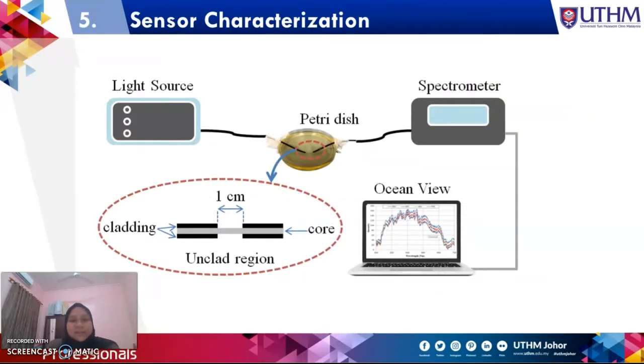For the sensor characterization, as we can see here, this is our light source, this petri dish contains the sensor head, this is the spectrometer, and the last one is the software that we use in this research, which is Ocean View. First, we switch on our light source, and then we test the transformer oil containing different levels of moisture, and Ocean View will generate the output spectrum for each different moisture level. As we can see here, this is the unclad region of the POF sensor, which we unclad to 1 cm. This is the cladding and this is the core.